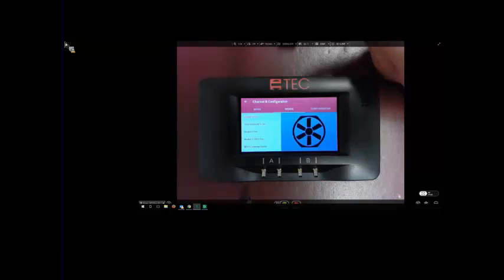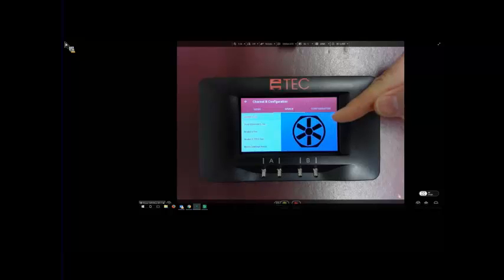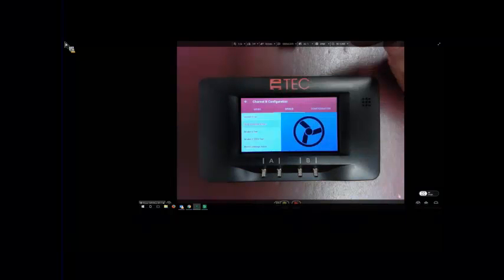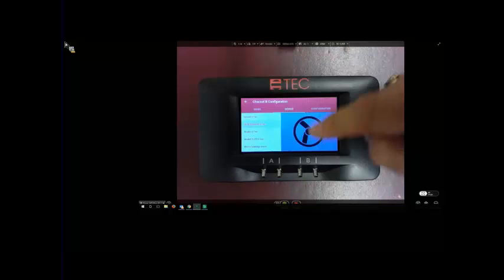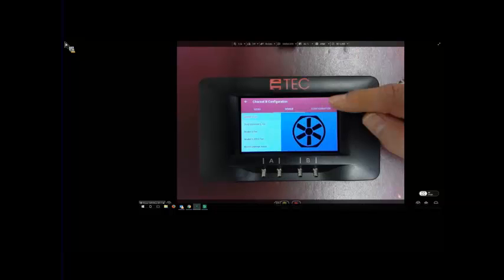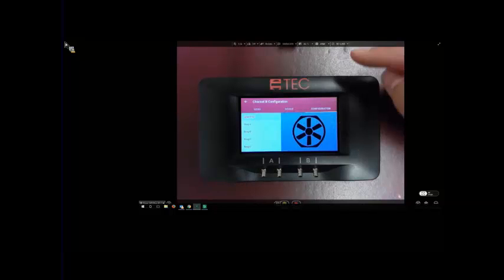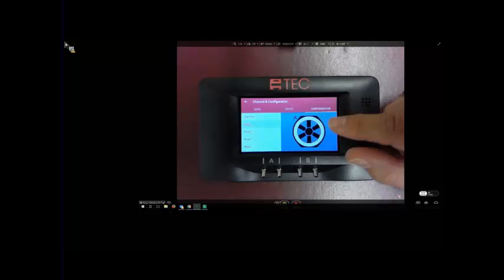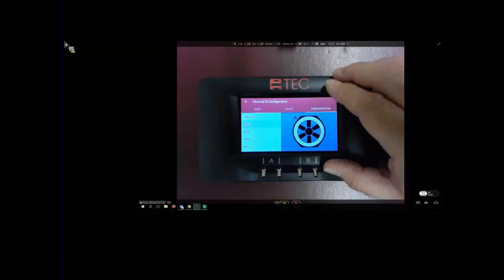Now I can set my device. You can see a graphical representation of your fan. So if I have the Model 3 fan, or if I have the DuctBlaster fan, you can make that adjustment and make sure that your system looks like what it is that you're testing with. And on the configuration, we now have the ability to pictorially choose what we have on there. So again, this allows the user to look at the gauge and compare that to the fan and the rings that are installed for the test. Does the gauge match what's actually being used to test?